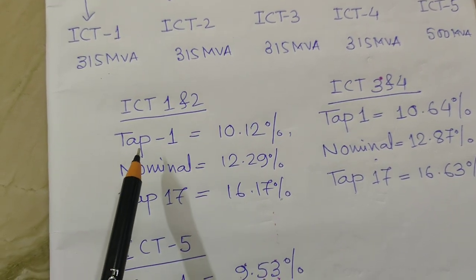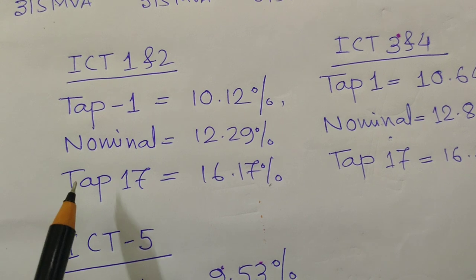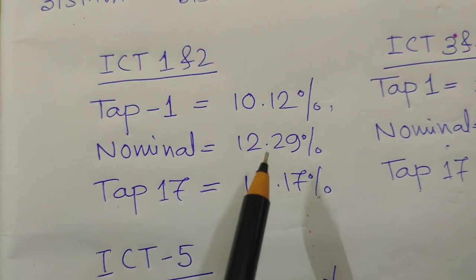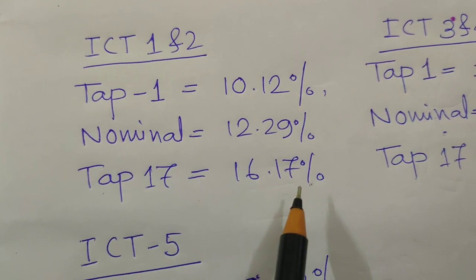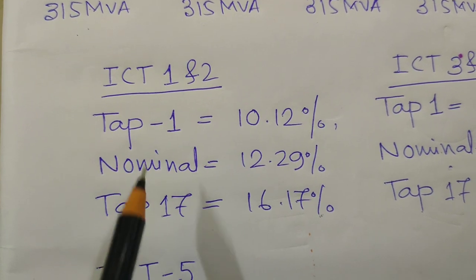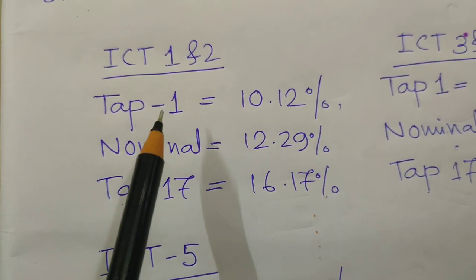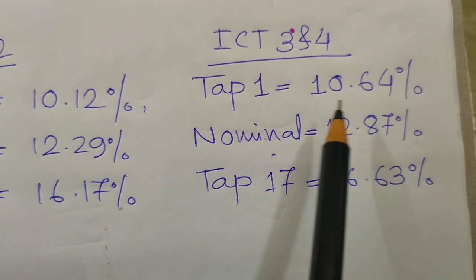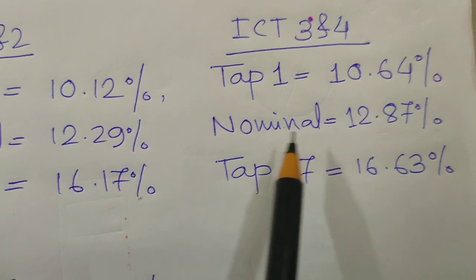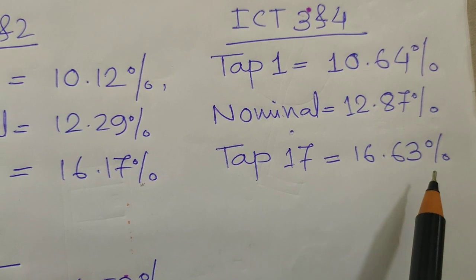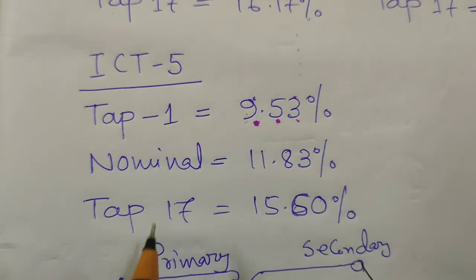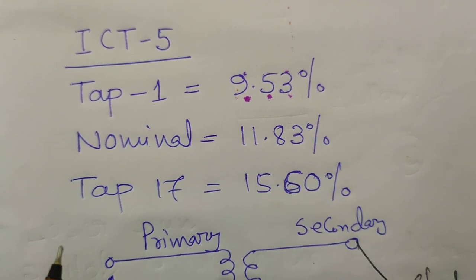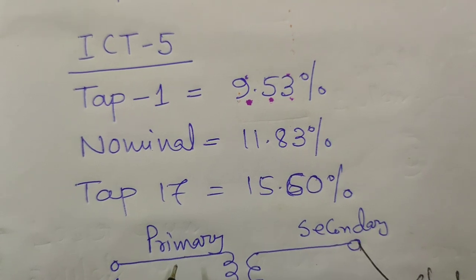ICT 1 has percentage impedance at tap 1 of 10.12%, nominal tap 12.29%, and tap 17 of 16.17%. ICT 1 and ICT 2 are the same transformer, so both have the same percentage impedance values across tap 1, nominal, and tap 17. For ICT 3 and 4, tap 1 is 10.64%, nominal is 12.87%, and tap 17 is 16.63%. For ICT 5, tap 1 is 9.53%, nominal is 11.83%, and tap 17 is 15.60%.